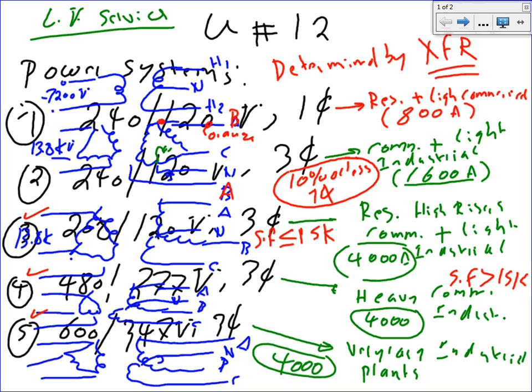That's the whole idea. Because as you go to higher voltage, the equipment gets more expensive. More efficient, but more expensive. The chiller that you're going to run at 480 is more expensive than at 208. All the equipment that you run at higher voltage is very efficient, but it gets a little bit more expensive. Any questions, guys, about 480/277?